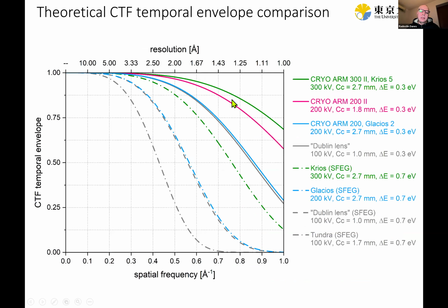And here you see in this plot the temporal coherence envelope simulated for a number of microscope configurations. So starting with the JEOL CryoARM 300 and Krios 5, they are both cold field emission microscopes with the standard objective lens pole pieces. This is the green curve. Now, there is a new CryoARM 300 version 2 with a narrow gap objective lens pole piece that was recently installed in Okinawa at the OIST.